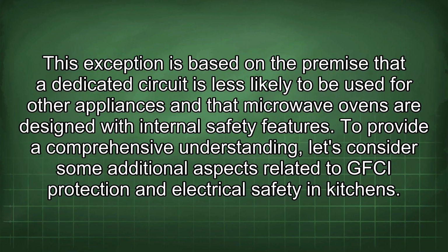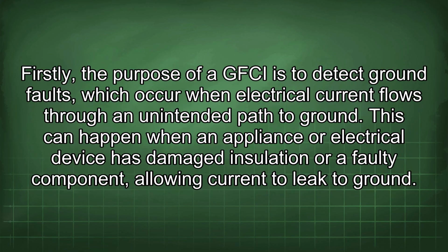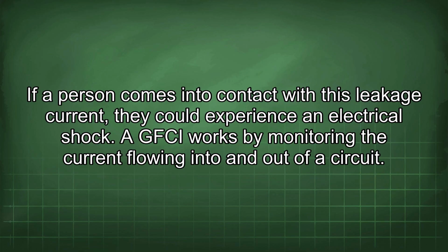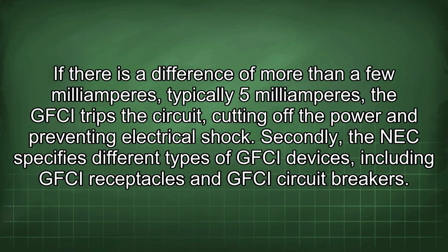To provide a comprehensive understanding, let's consider some additional aspects related to GFCI protection and electrical safety in kitchens. Firstly, the purpose of a GFCI is to detect ground faults, which occur when electrical current flows through an unintended path to ground. This can happen when an appliance or electrical device has damaged insulation or a faulty component, allowing current to leak to ground. If a person comes into contact with this leakage current, they could experience an electrical shock. A GFCI works by monitoring the current flowing into and out of a circuit. If there is a difference of more than a few milliamperes, typically 5 milliamperes, the GFCI trips the circuit, cutting off the power and preventing electrical shock.